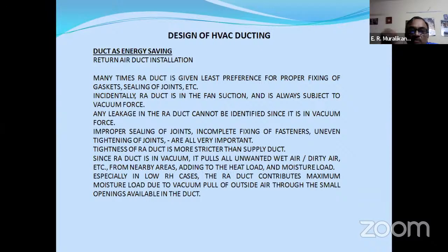But return is in vacuum. You cannot see or feel vacuum. So if the duct flange bolts are not put properly, the gasket not put properly, what will happen? It will pull all the unwanted material from the surroundings, add to dust, and add to heat load and everything. But it's not visible. You cannot sense or see any return duct leakage.